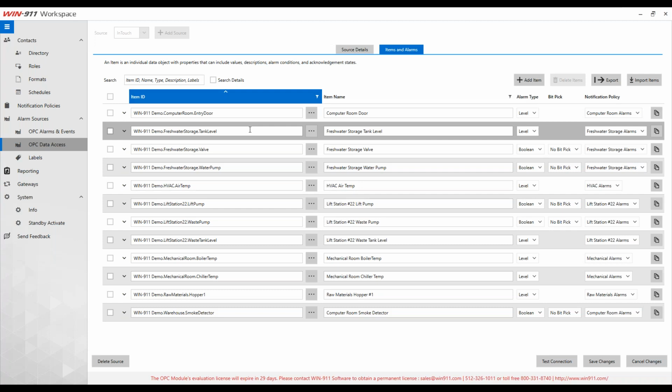But one of the things that we'll make available soon are setup guides for different SCADA systems, whether it's with the alarm and event module or the data access module. So I know that some of our customers don't like our InTouch Direct Connect because the toolkit that is available through Aveva is sometimes not reliable. It's hard to set up remote connections, especially if you have a terminal services environment. Well, you could connect through OPC DA instead using the acknowledgement sync option, and you can just paste in all your descriptions and everything with that Excel import instead of doing it the other way.